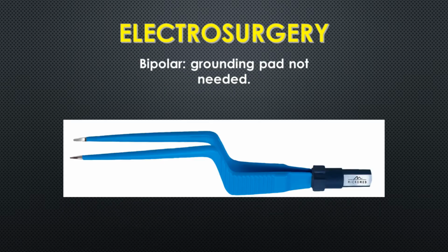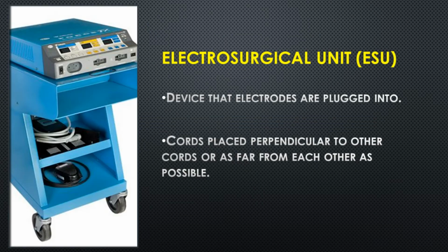In bipolar electrosurgery, a grounding pad is not needed because the current only travels through the tissues between the tips of the bipolar forceps. The electrosurgical unit, or ESU, is the device that the electrodes are plugged into to incise tissue or control bleeding by causing the coagulation of blood.